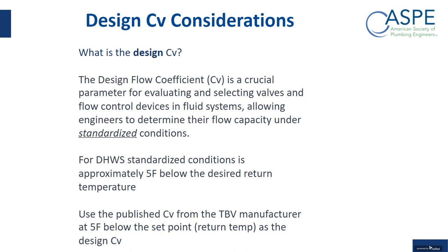The thing I'm cautioning you about here is that with the adjustable thermostatic balancing valves, you'll see design CVs all over the place. Some of them will have them at 90 degrees Fahrenheit. Some of them will have them at 110. So to be consistent and to have a better performing system, you need to either look at the curves or the data presented by the manufacturer, or ask the manufacturer, what is your CV at 5 degrees Fahrenheit below your return temperature?